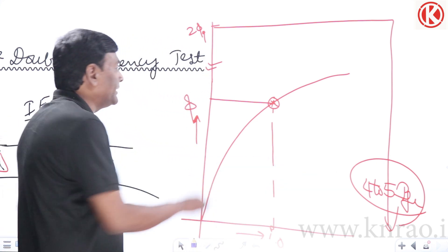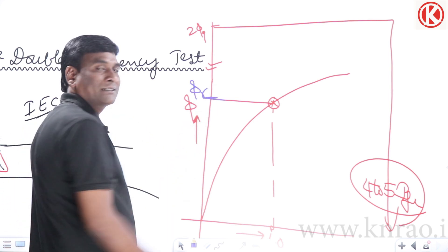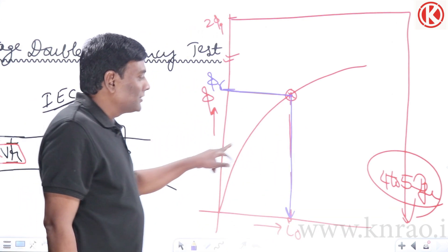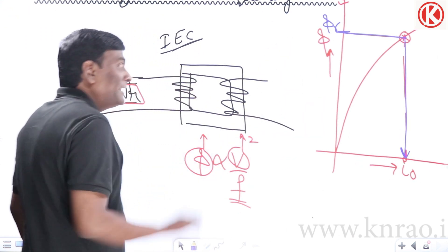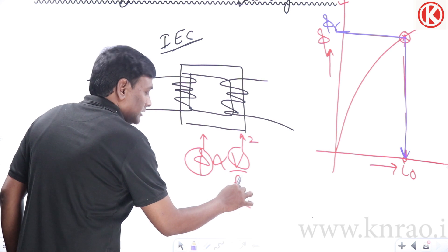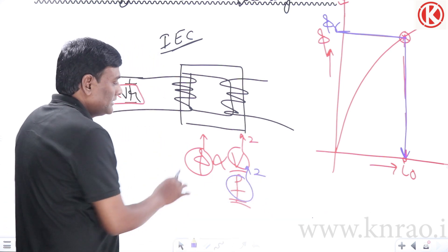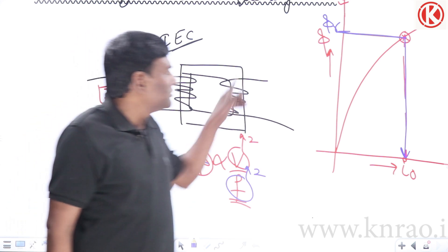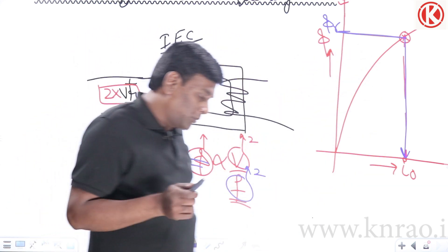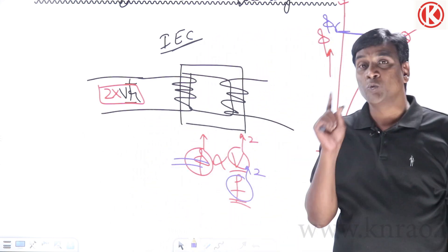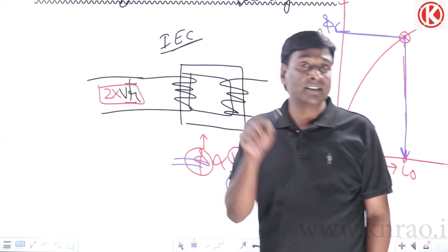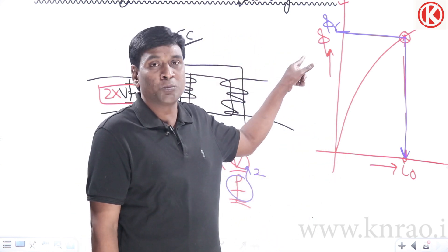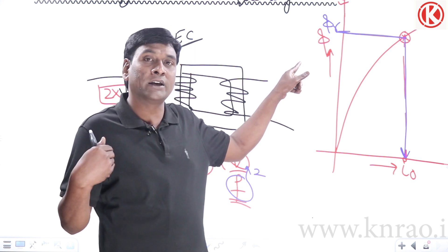So the operating flux must not be increased — whatever the rated operating flux density B-max is, it should remain the same. To maintain the same operating flux while doubling the voltage, the frequency must also be doubled. That way the V/f ratio stays constant and the operating flux stays the same, so the four-to-five times full load current will not flow and the same no-load current will flow.